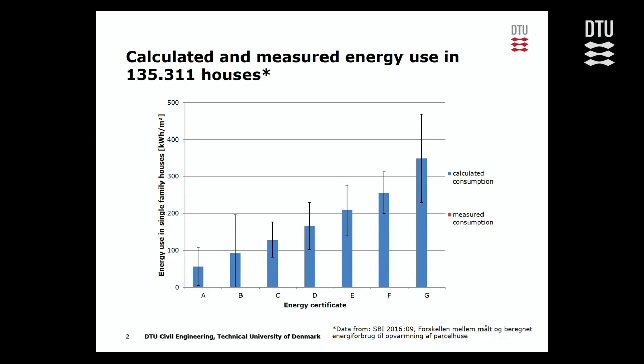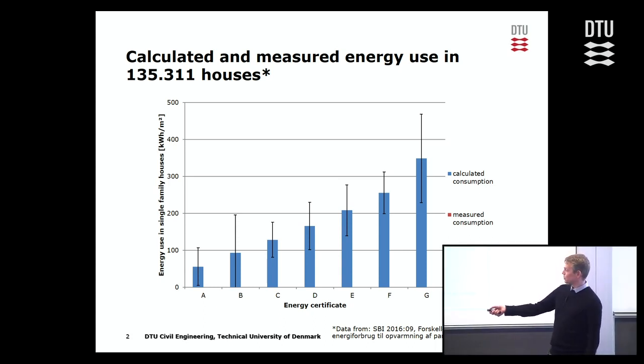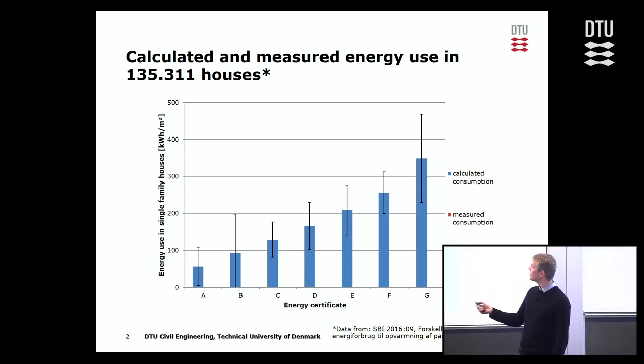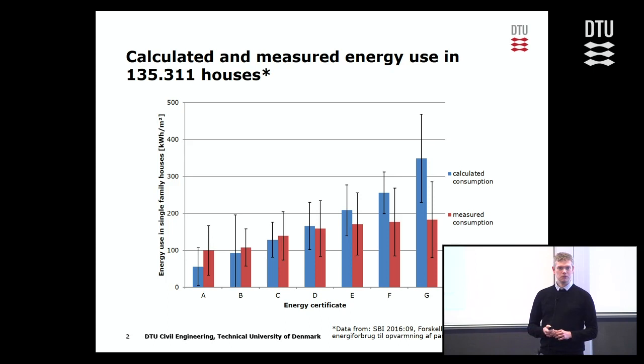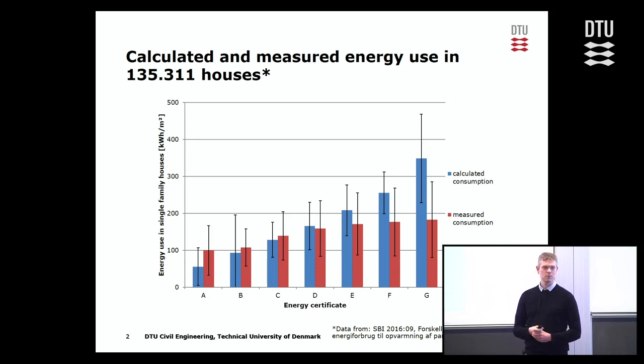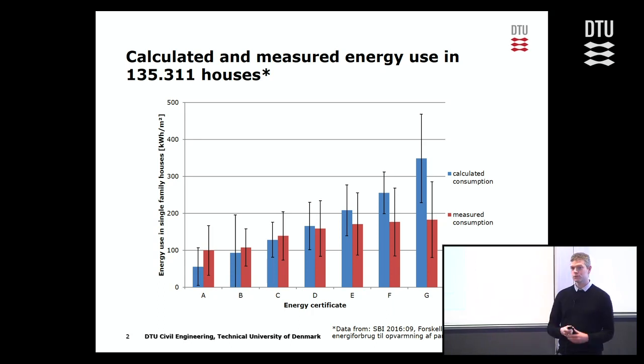This is data from a report from the Danish Building Research Institute. They compared 135,000 energy certificates in Danish houses. Here we have the energy certificates and the energy use - the calculated consumption shown in blue. What's interesting is to compare with the measured consumption. If you live in an energy efficient house, you actually spend twice as much on average as the energy certificate states. But if you live in an energy inefficient house, you spend only half of what the energy certificate states.